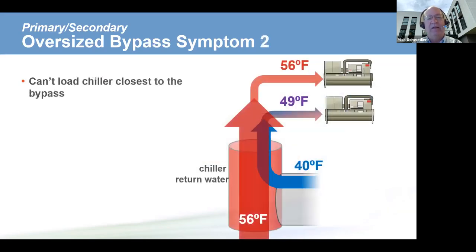Another symptom, on the return side: that 40 degree water that's coming through the bypass line doesn't mix because it's going at a very slow velocity. And the first chiller after the bypass line receives a lower return water temperature. And we can't get that chiller to load because in a primary secondary system, its flow rate is constant. So in this case, it can only load to 9/16 of its load, under 60% of its load. And then the chillers down the line get the higher water temperatures.